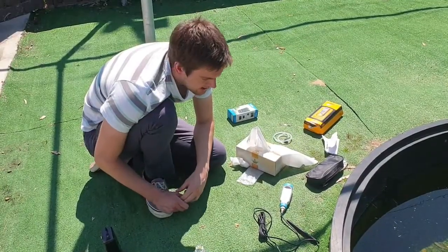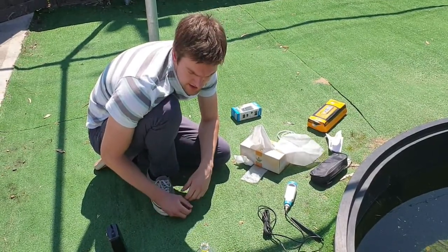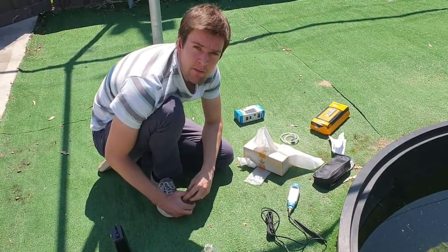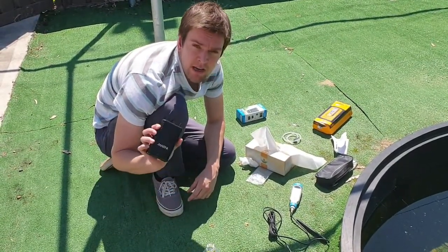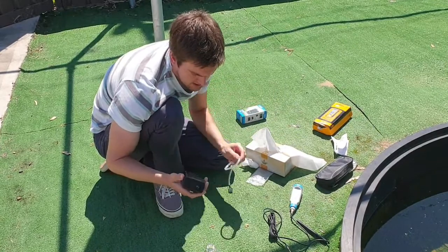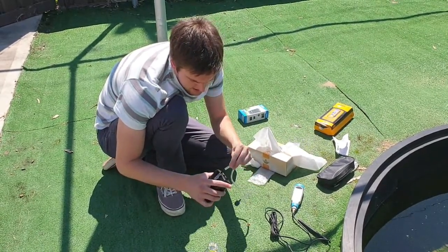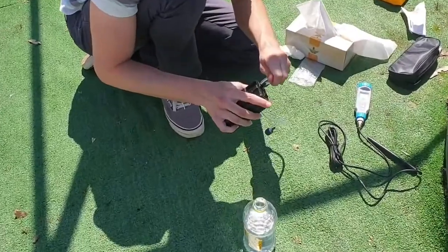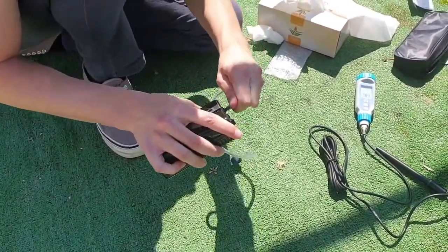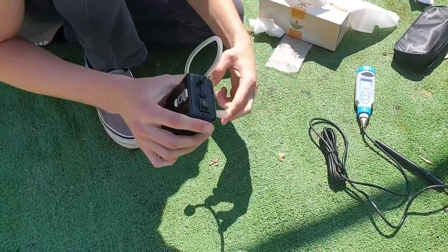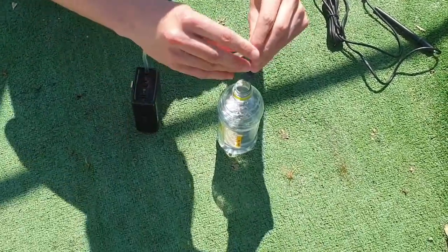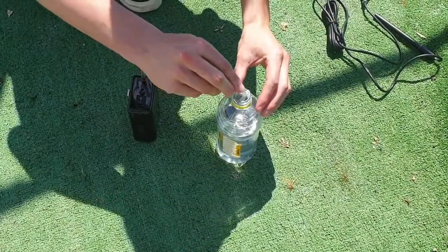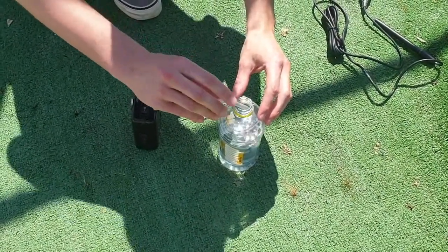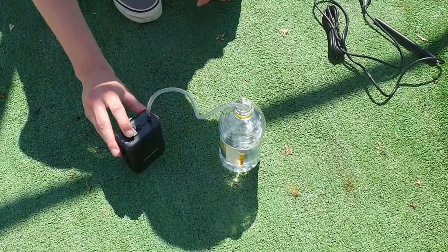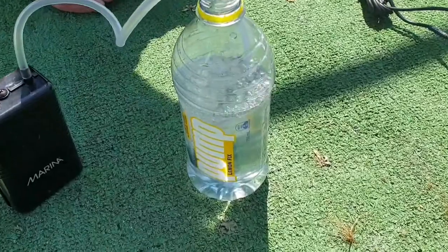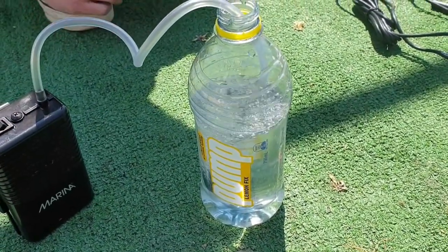The next step in the 1 point calibration is that we need to bubble some fresh water for a minute. So we're going to use a simple air pump to do this. So we simply attach this tube to the air pump, insert the tube and the air stone into this container, switch on the pump, and we bubble the water for a minute before immersing the probe.